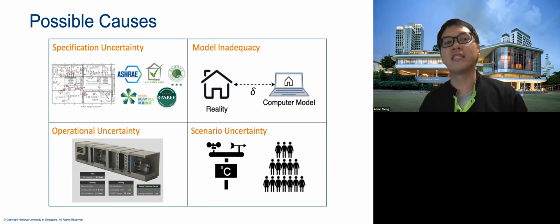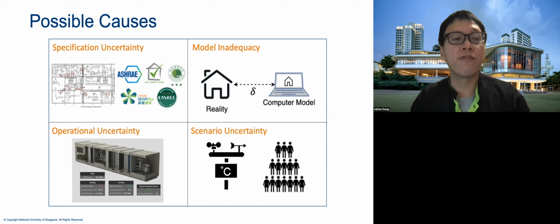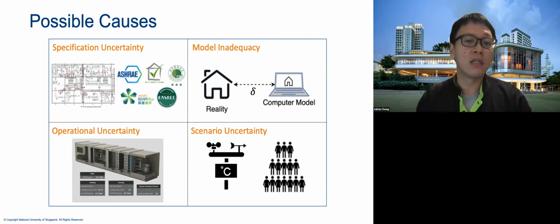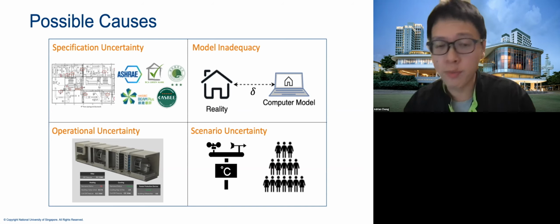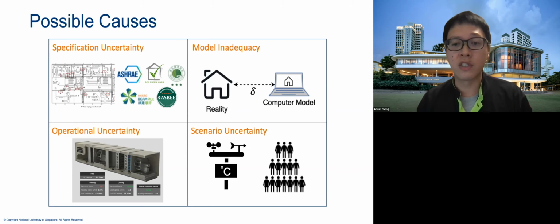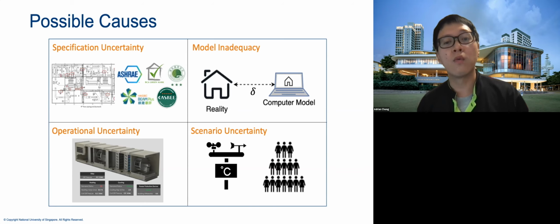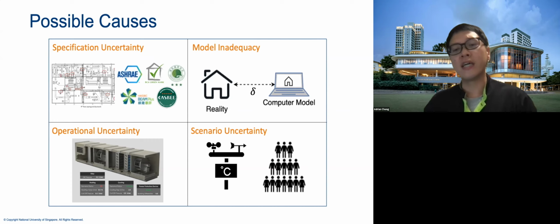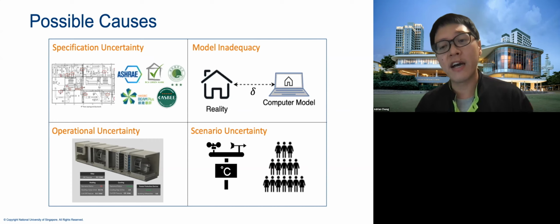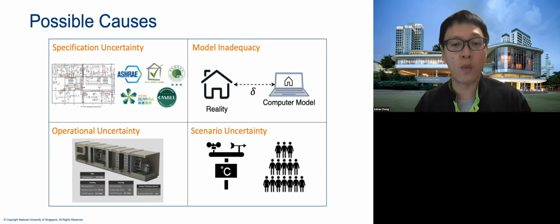For instance, during the design phase, certain assumptions are made regarding the supply air temperature—it could be 13 degrees Celsius—as well as the fresh air supply. But in actual operation, that might not match what was assumed during design, or it could have changed during operation to suit the building's current needs. Lastly, there is scenario uncertainty arising from specifying model conditions such as weather and building occupancy.